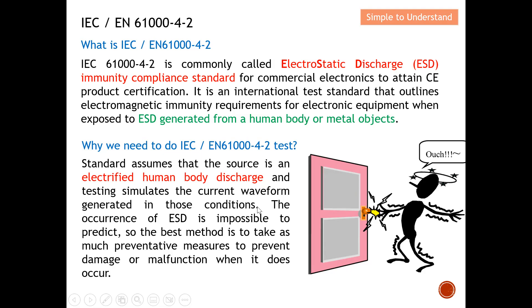The occurrence of ESD is impossible to predict, so the best method is to take preventive measures to prevent damage or malfunction when it does occur. We cannot predict how severe the ESD effect will be, so we take preventive measures to ensure the device is robust. When a human discharges into our EUT or DUT, we want our device to continue functioning as intended. That is why we emulate this test using IEC/EN 61000-4-2.